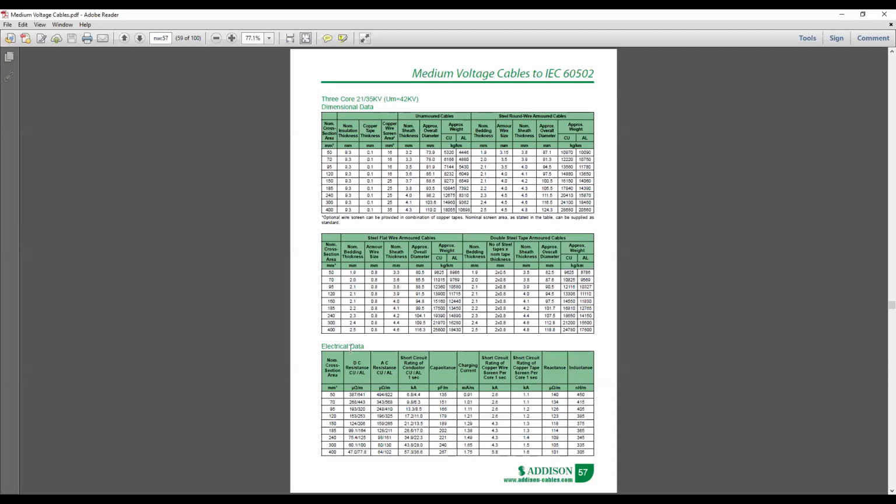In the voltage drop criteria, you may remember we used the resistance per kilometer values and reactance per kilometer values. So all those things are included in here. Actually they have copper and aluminum conductors. That's why they have separated these two values. So the first value is for copper and the second value is for aluminum.